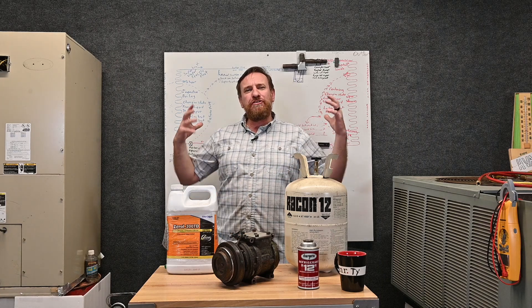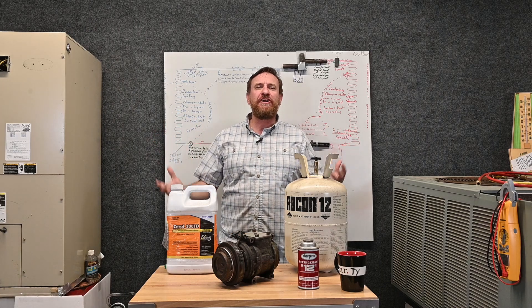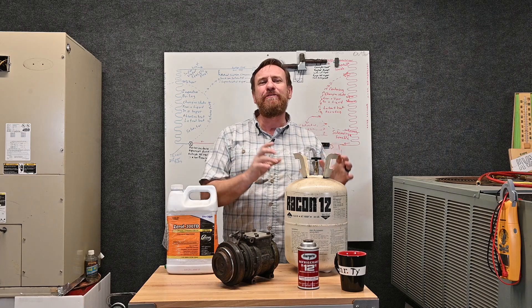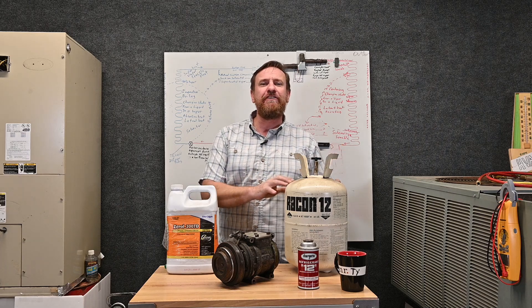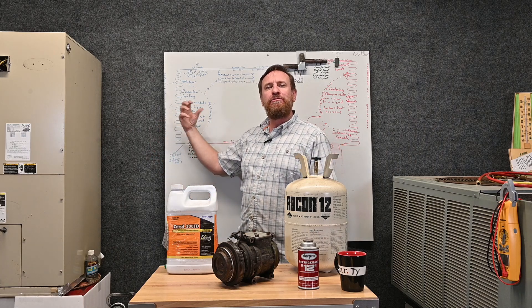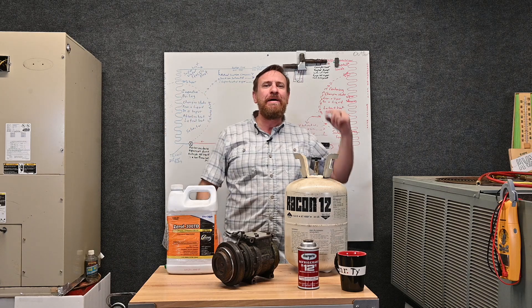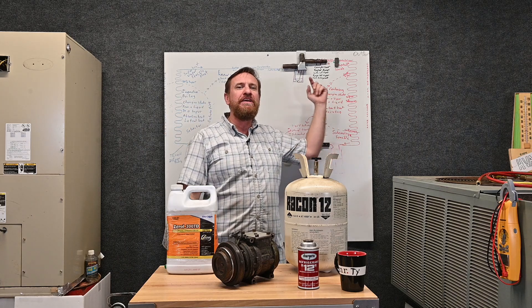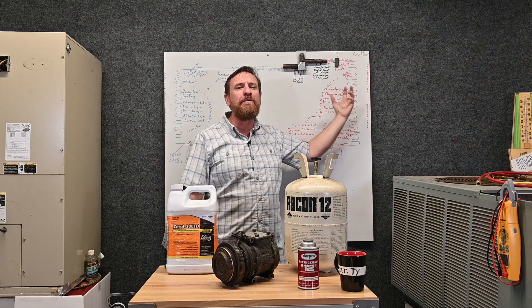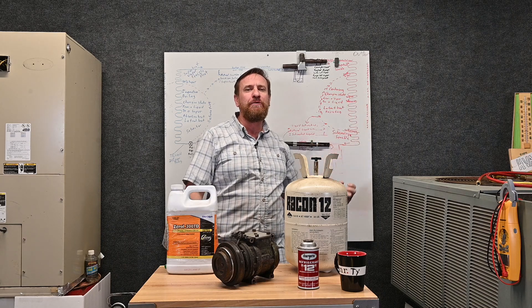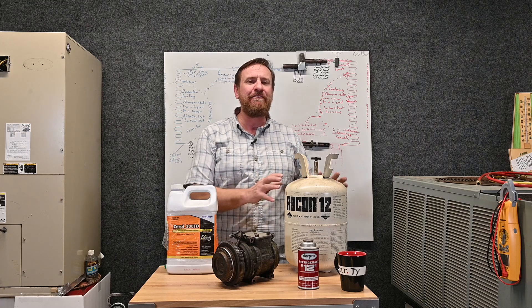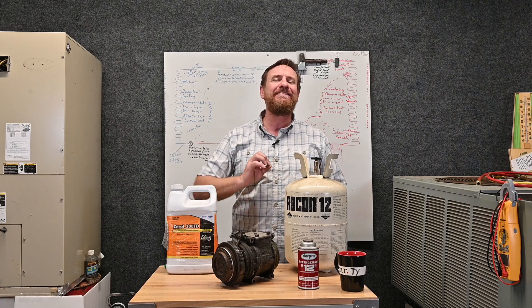We've hammered in the importance of the refrigeration cycle, but just as important as the refrigeration cycle is the refrigerant itself. Remember that refrigerant changing state from a liquid to vapor absorbing heat, then we superheat it back to the compressor, desuperheat it, make it change state from a vapor back to a liquid, then we sub-cool that liquid. That change of state and the latent heat of that refrigerant is essential.